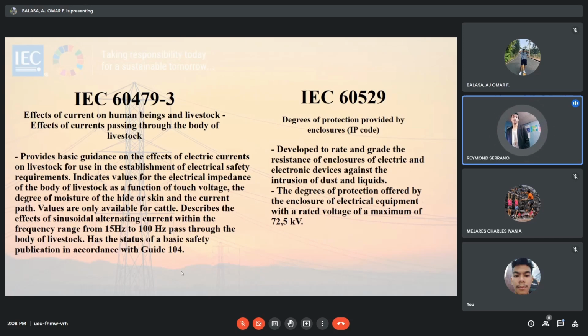This technical report indicates values for the electrical impedance of the body of livestock as a function of touch voltage, the degree of moisture of the skin, and the current path. At this time, values are only available for cattle, so the effect of sinusoidal alternating current within the frequency range from 15 Hz to 100 Hz passing through the body of livestock. So take note, unless otherwise specified, the current values defined in the technical report are RMS values.